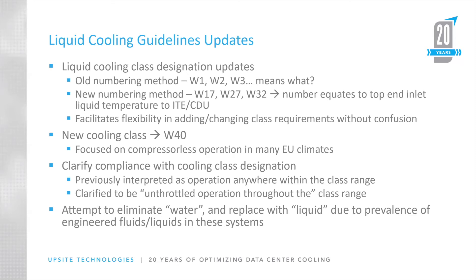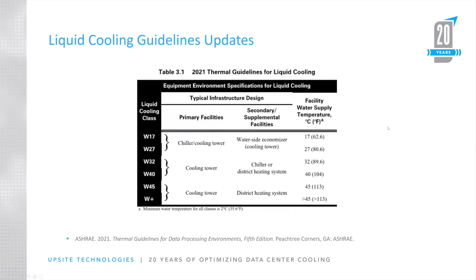Here is the updated table. The primary change is the temperature designations — W17, W27, W32 — as opposed to W1, W2, W3. W40 is a new classification added here. The old W5, which covered anything over 45 degrees centigrade, is now called W-plus, since there's no real upper bound on it.